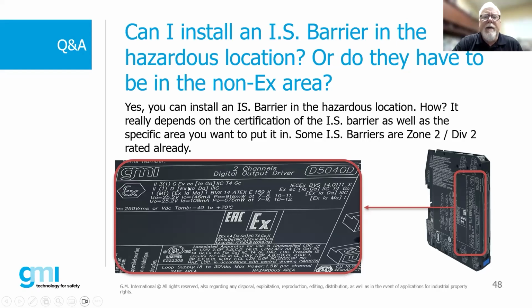It's saying, in effect, the output for this barrier can actually go into a Zone 0. That's what that marking string is basically telling us. Now, if you're familiar with the North American side of things, look below and you'll see, next to the UL listed mark, it'll say Class 1 Division 2, Groups A, B, C, D, Class 1 Zone 2, and so on.